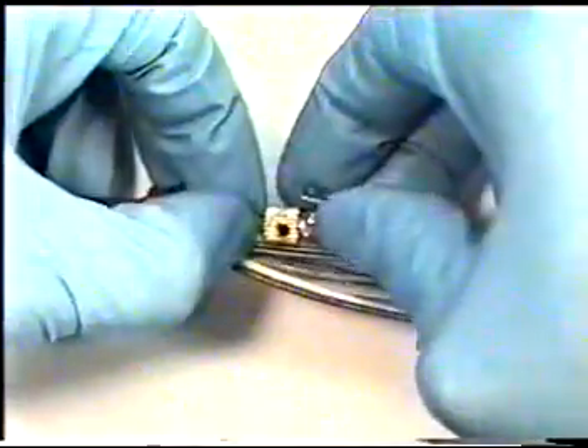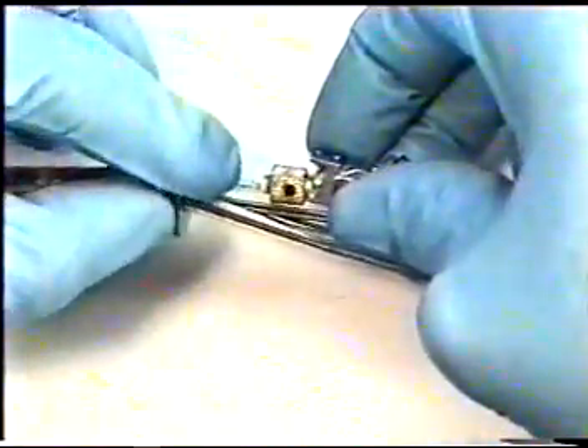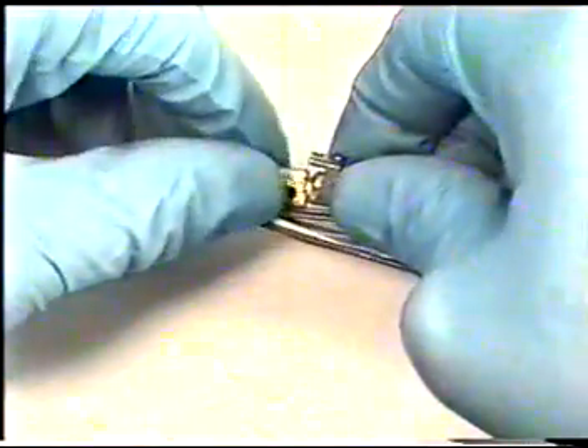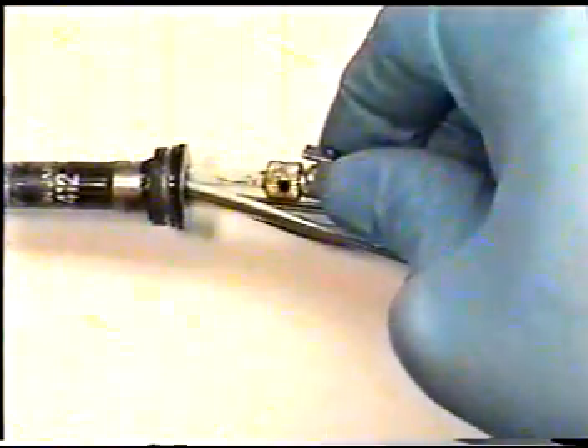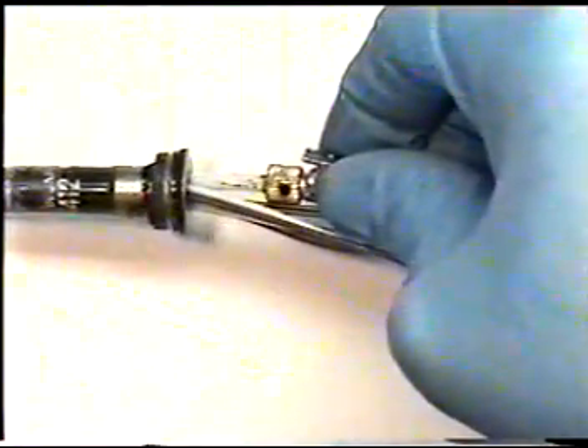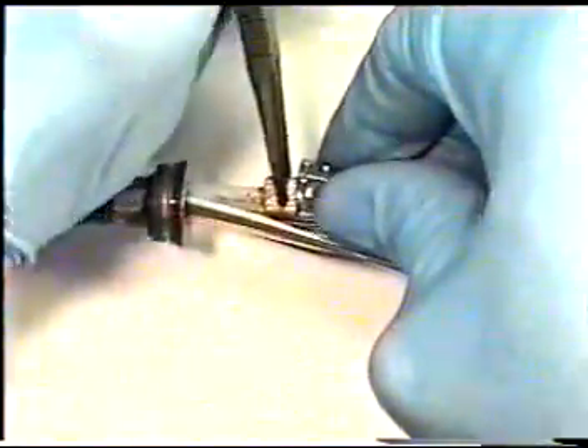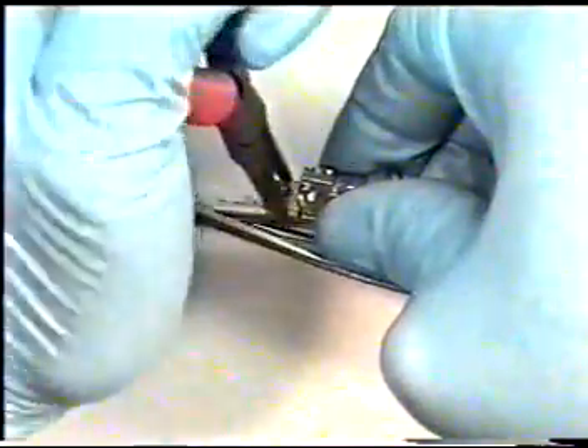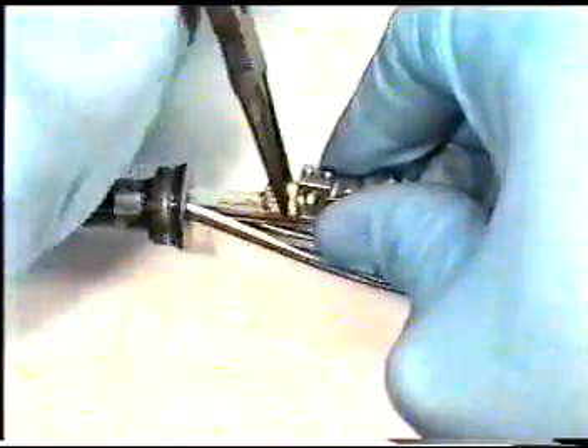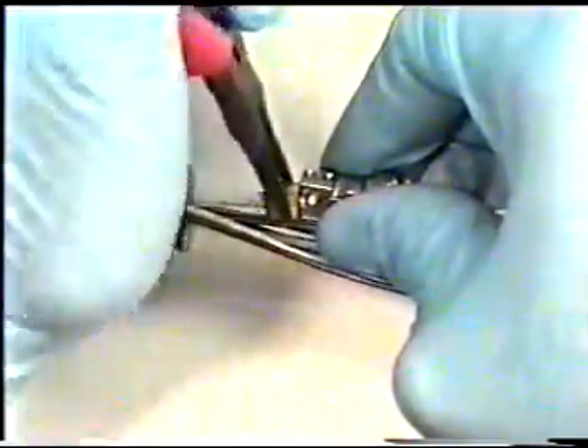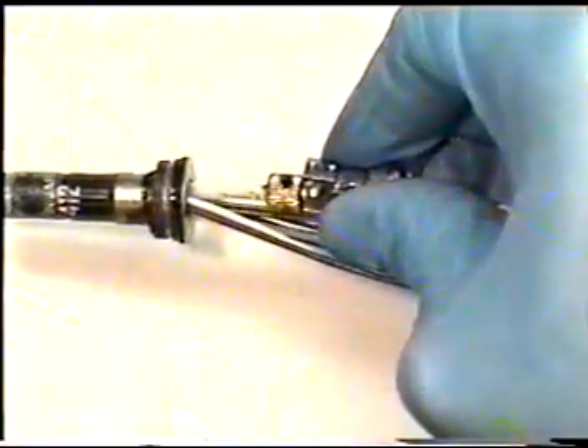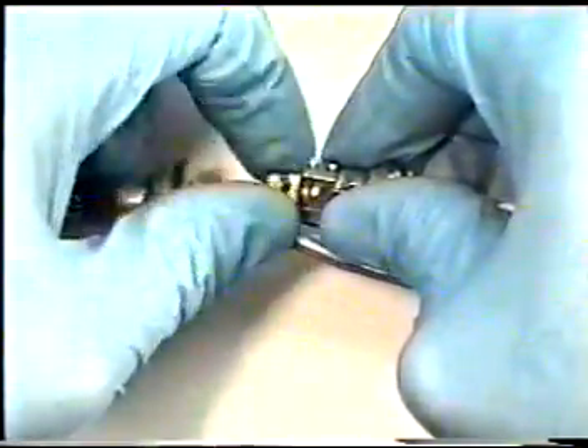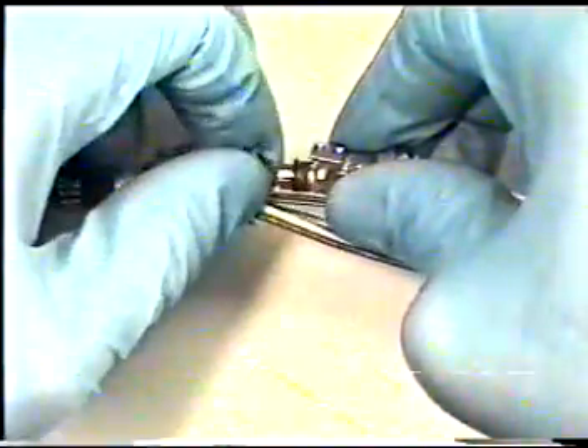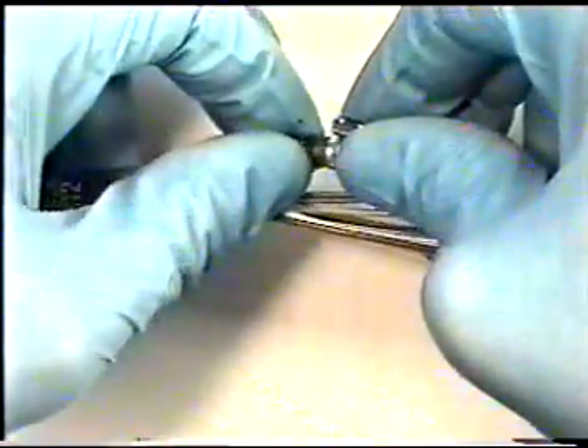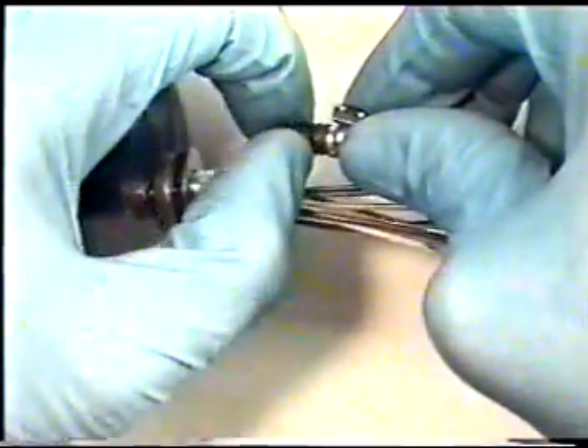We'll need to detach our biopsy channel from our biopsy channel forceps assembly using a small pair of needle nose pliers. Unscrew 2 ferrules counterclockwise, making sure that you do not pinch or damage any of the tubes, coil pipes, or wires. Carefully slide off biopsy channel and remove 2 locking ferrules.